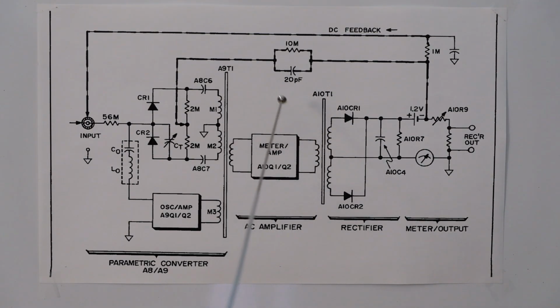So I believe this instrument can measure something like 10 to the 15 or 10 to the 16 ohms, which is extremely high. And of course for those types of values you would have to apply a 1 kilovolt DC level. It can also measure at lower voltages, but then your maximum resistance that can be measured is lower. So this is a fairly versatile instrument that can measure from a few megohms to hundreds of teraohms or even beyond.